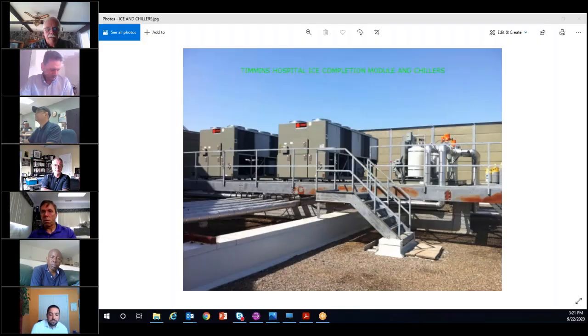Where this started essentially was they had 4 existing chillers. They were air-cooled chillers, about 150 tons each. They were 20 plus years old, so they were nearing end of life. The specific challenges that the client had, they actually had the nice problem of having excess capacity. So they really only ever ran 2 out of those 4 chillers, and certainly any hospital will enjoy having redundancy, but that may have, for them specifically, actually been more than they needed and was potentially resulting in additional maintenance costs. They certainly wanted to improve dehumidification and temperature control in some of their critical zones through the hospital.